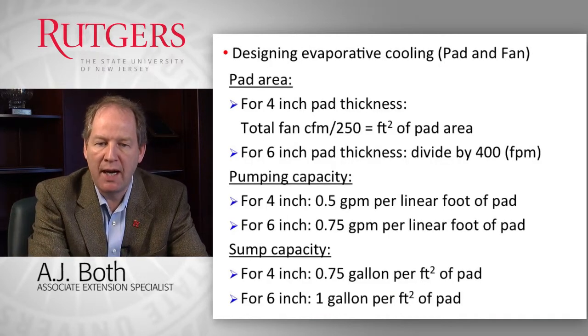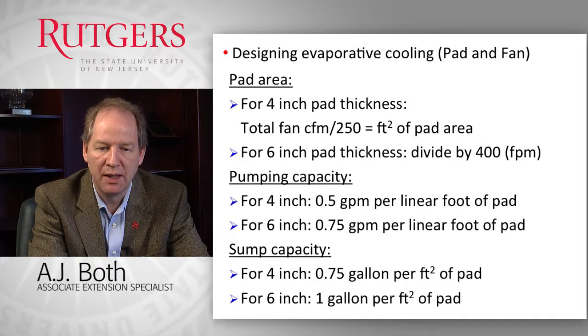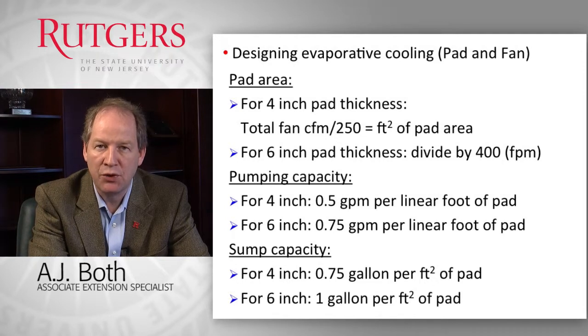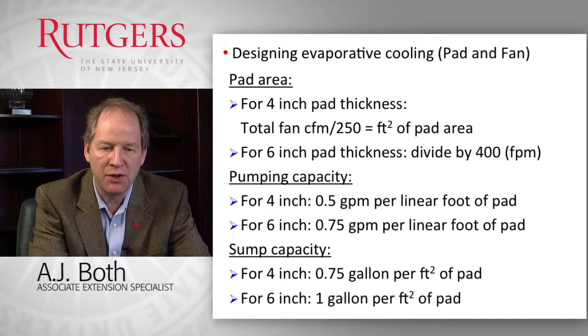Some information about how you design an evaporative cooling pad and fan system. There are different thicknesses of pads used; the most typical is four inches, but sometimes people use six inches. To figure out the total pad area required, you need to know your total ventilation fan capacity in CFM. Divide that by 250 to get the square footage of pad area when using a four-inch pad thickness. For a six-inch pad thickness, divide the total fan CFM capacity by 400.